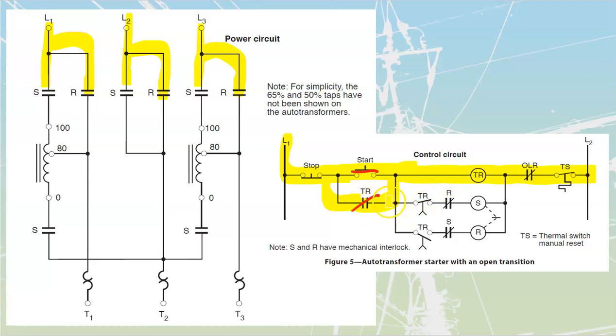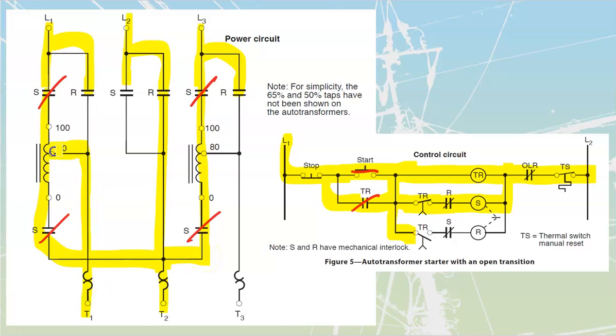I also see that I've got a normally closed contact and a normally open. The normally open is going to stop the current. The normally closed is going to pass it through to my starting contactor. So I'm going to close any S's that I have, which is going to be this one, and this one, this one, and this one over here. When I close those, we have now set up complete paths for current flow. If I highlight those, we should see that this is going to go through to there, this is going to go through there, and this is going to go through to there. And from there, we can pass on down to our actual motors through here.